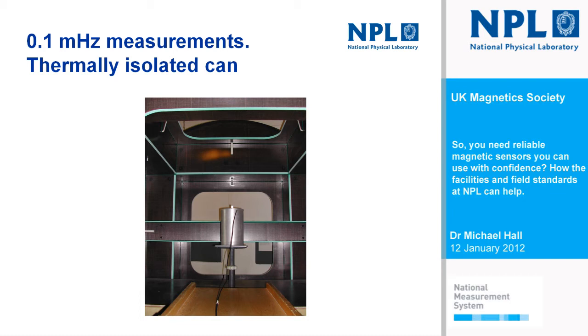We also have to be aware here of thermal drifts, so we have to thermally stabilise this 3-layer can, and to do that we've put it into a thermal chamber and measured the temperature inside that chamber over a period of over a day, and it's very, very good. In fact, you can see there on the third bullet point it's 0.05 degrees centigrade over a 24-hour period, so thermally it's been nicely stabilised. And we need to do that because if the temperature is drifting, then we have a fluxgate magnetometer in there to measure what the field is. That will also drift because the offsets have a temperature coefficient, and that will therefore appear as some noise.